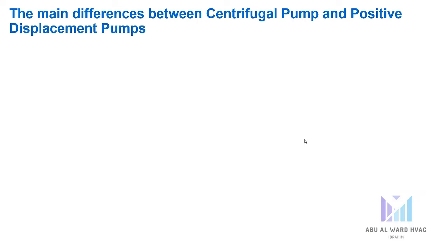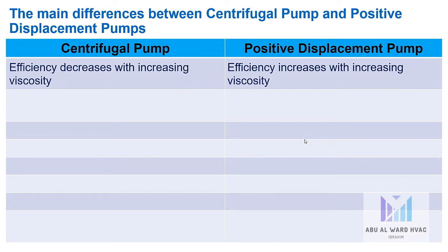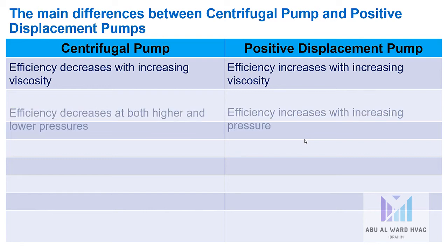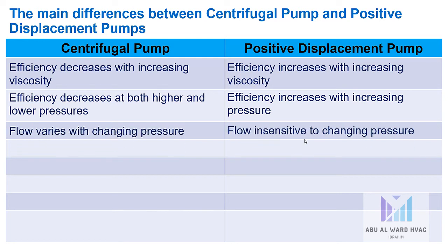Here are the main differences listed in a summary table. Centrifugal pump efficiency decreases with increasing viscosity, while positive displacement pump efficiency increases with increasing viscosity. Centrifugal pump efficiency decreases at both higher and lower pressures, while positive displacement pump efficiency increases with increasing pressure. Flow varies with changing pressure in centrifugal pumps, but is insensitive to changing pressure in positive displacement pumps.